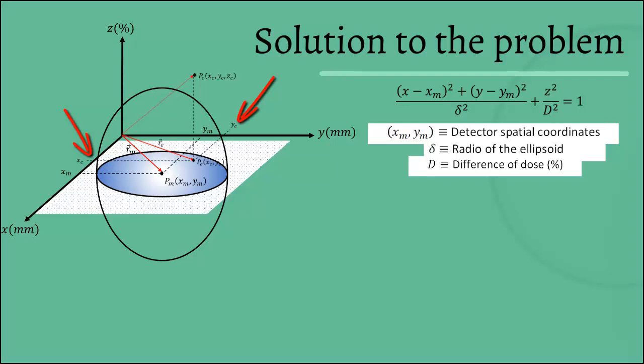The value ZC is a difference of dose and it could be compared in a local manner, which has to do with the comparisons of dose calculated on that point against the measured dose by the detector.